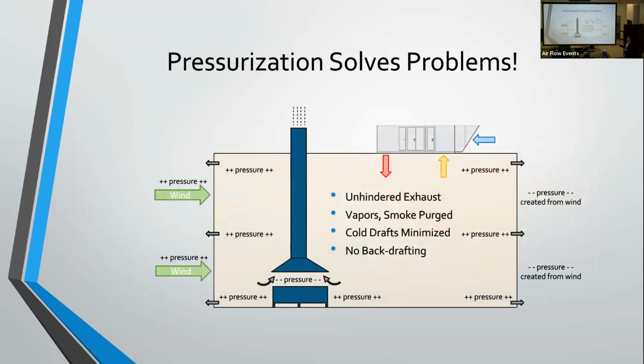Yeah, this was supposed to be a visual for what I was just talking about. I'm used to the button click, sorry about that. But anyway, this is just kind of a visual of what's happening here. Basically, you've got your makeup air pushing your air into this space here. You've got a lower pressure on the outside of the building, and actually you've got some interesting concepts here where wind pressure on this side of the building creates a lower negative pressure on this side of the building, which helps push this air from inside the building out even more so. So not only are you pushing the air against that wind pressure there, but you're also pushing it out from this side of the building also.